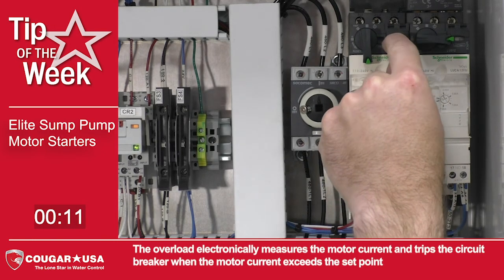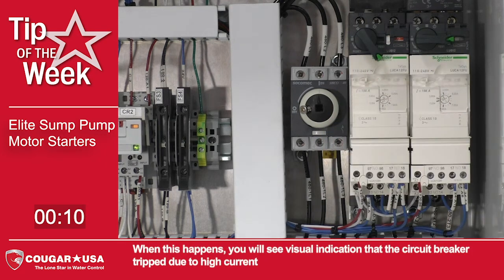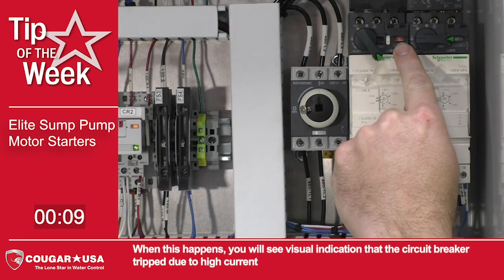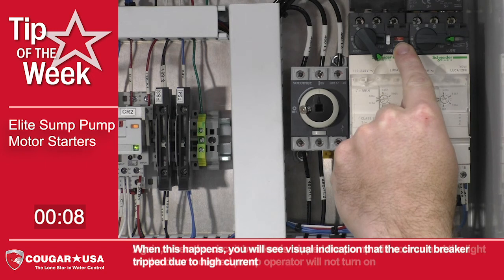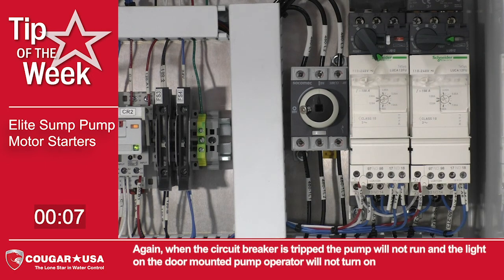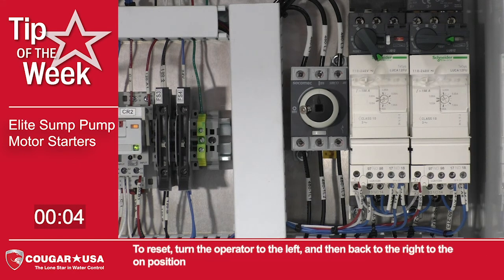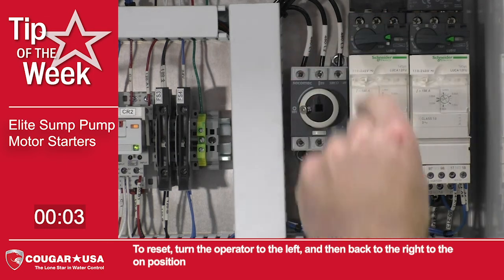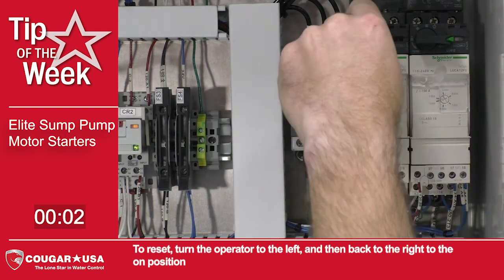the set point. When this happens, you will see visual indication that the circuit breaker tripped due to high current. Again, when the circuit breaker is tripped, the pump will not run and the light on the door-mounted pump operator will not turn on. To reset, turn the operator to the left and then back to the right to the on position.